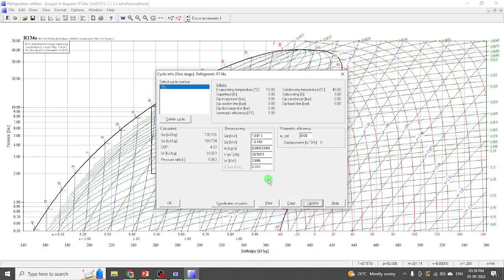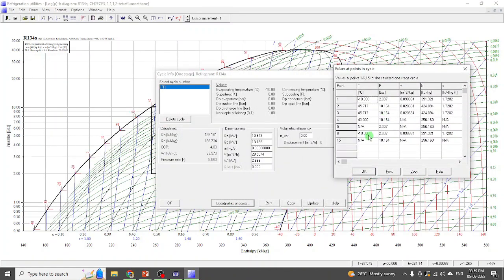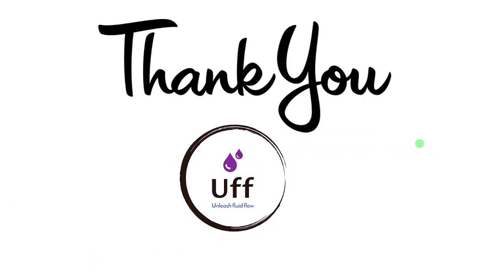If you have the refrigerant flow rate, you can put that value here — for example, 0.08 kg per second — click the update button, and you will get the actual heat absorbed in the evaporator in kilowatts, heat rejected from the condenser in kilowatts, work input in kilowatts, and all other values. You can also click on another icon to find the coordinates of each point. That's all from this video on how to use CoolPack software for a simple vapor refrigeration problem. Please subscribe, like, share, and comment.